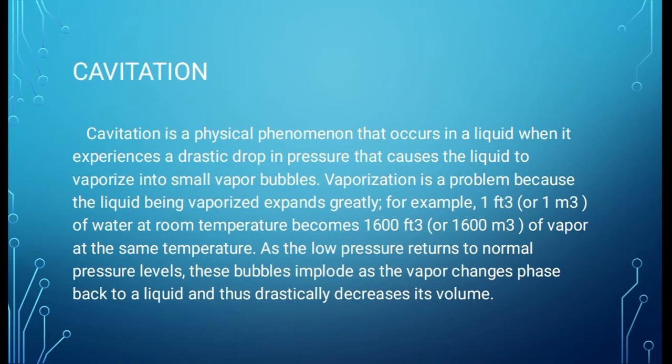The noise that develops sounds similar to gravel flowing through the system in the area where the cavitation is developing. Over time, the erosion results in excessive wear. This eventually manifests itself as pinhole leaking. Ito po yung worst case scenario natin. Kapag nangyari to, get ready na po tayo para sa gastusin for repair and installation.